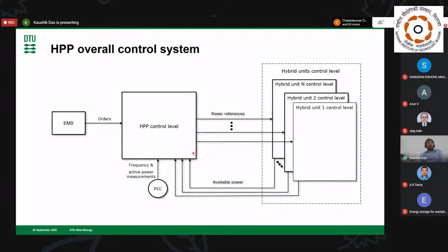And similar control functions like we saw there - you have the hybrid unit dispatch and the hybrid controller inside here. You have the dispatch function and then the hybrid unit controller, because in this you get the set point in the inverter, and then you have to send the signal to the individual wind turbine, solar PV panel, and battery storage.